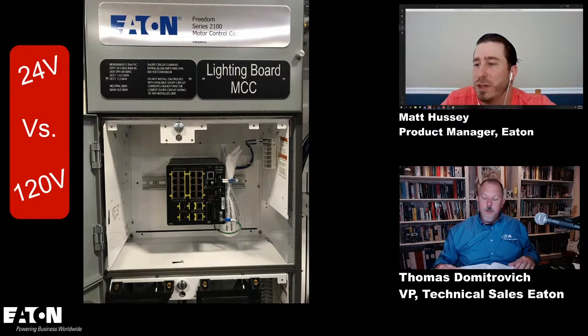So the challenge you'd have is that this unit doesn't have any power connections to the bus, so that element's going to be needed. You're also going to need an actual circuit breaker or fusible disconnect to feed that unit. A lot of that sheet metal, as you can see, doesn't have all the mounting provisions for that. So usually the easiest path is that you end up getting either a spare unit or a replacement unit installed with all the appropriate fixings, if you will, to be able to feed that drive.